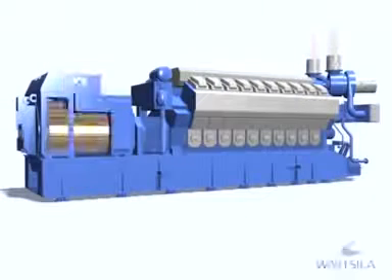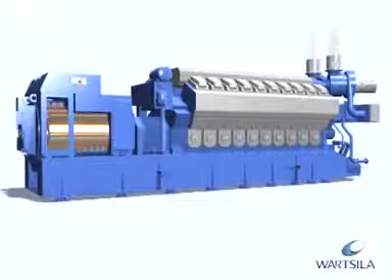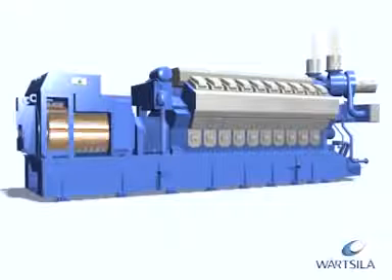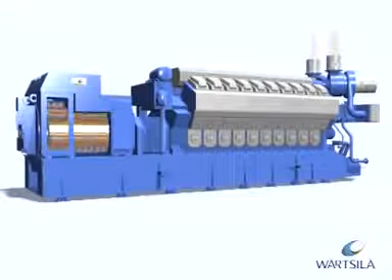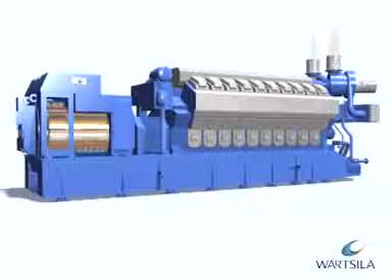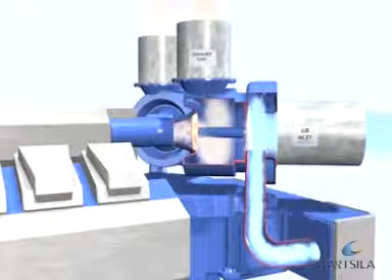The engine generating sets used in Wärtsilä power plants are driven by heavy-duty medium-speed four-stroke reciprocating engines. These generating sets consist of an engine connected directly to a generator via a flexible coupling. The generator and engine are rigidly mounted on a common base frame, which in turn is mounted on steel springs on the concrete foundation. The engines are equipped with turbochargers and charge air cooling.